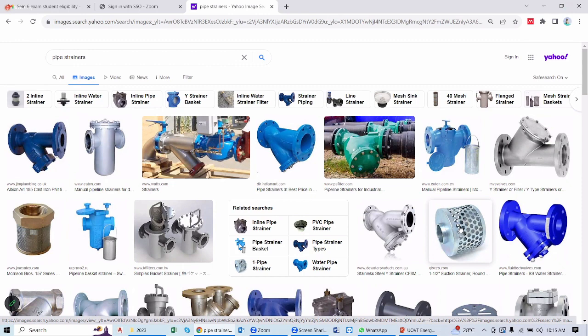because there'll be a lot of impurities inside the piping the moment you do the first run. There'll be even metal parts after the welding process and any corrosion. So those things will actually get collected. So during the first commissioning stage, you have to ensure that these strainers are cleaned frequently, and you take out all the impurities in the system. Once the first run is done, generally it is less headache with the strainers, but I don't know whether there's an automatic method of looking at these systems. At least during maintenance and overhaul, you have to ensure they are cleaned up.